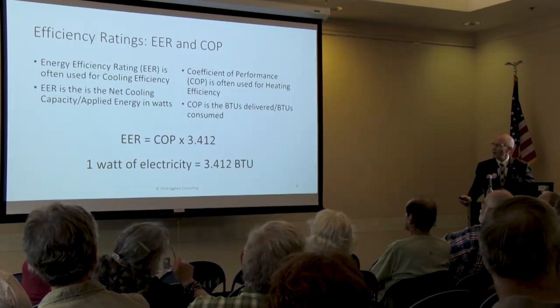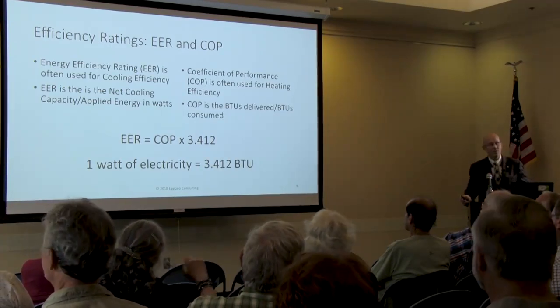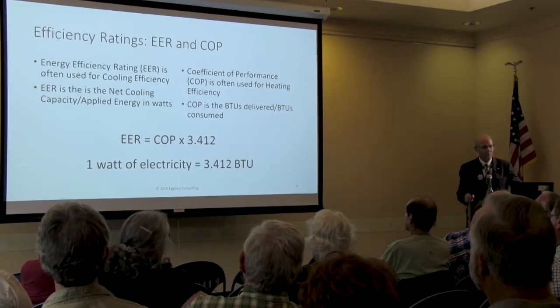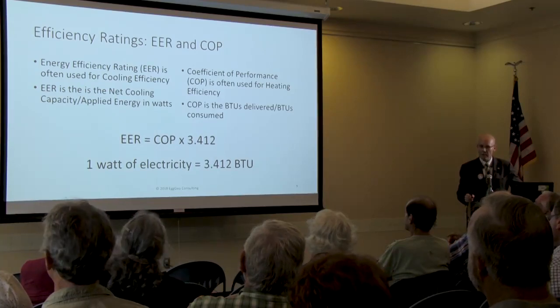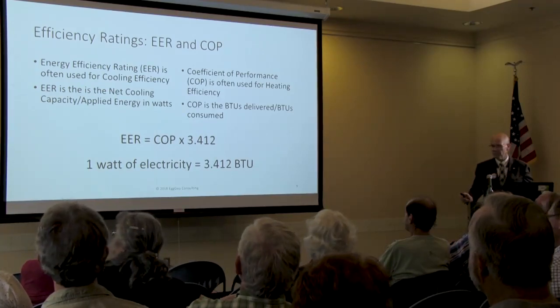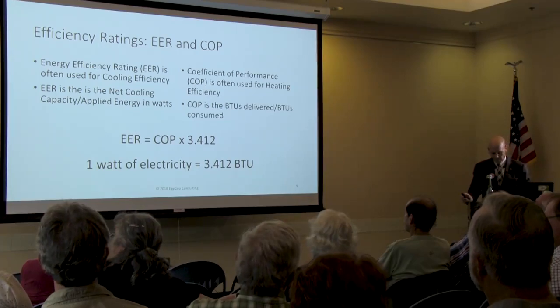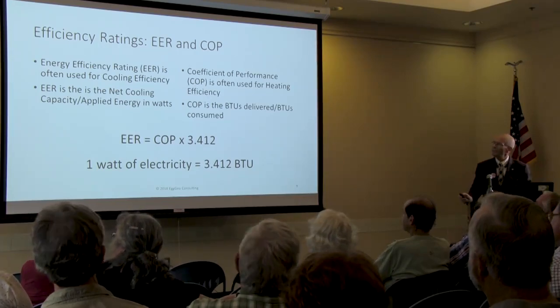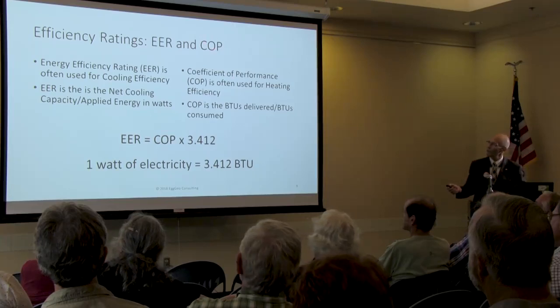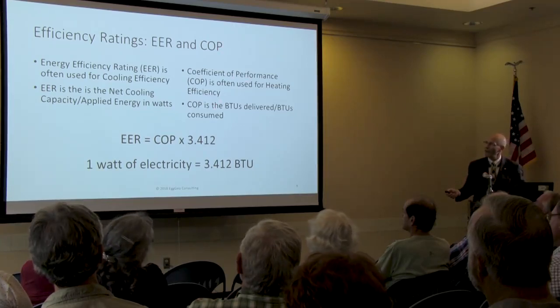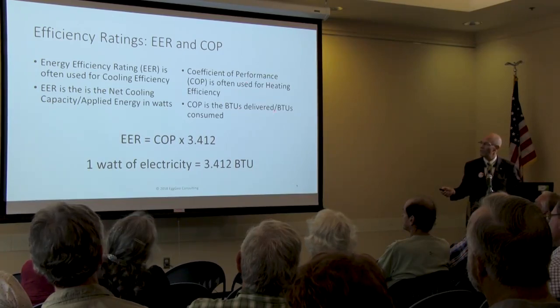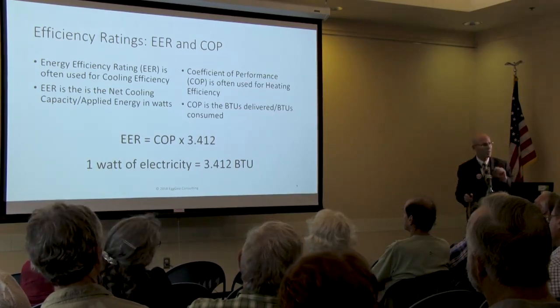I want to talk just a minute about energy efficiency ratings and coefficient of performance. This gets a lot less dry in a little while, but this is important for the basis of this. Heat pumps and systems in general, any system is rated with a COP, a coefficient of performance, and it's simply the BTUs delivered divided by the BTUs consumed. This can also be, it doesn't matter, like units, kW delivered divided by kW consumed, and that's how it's done.